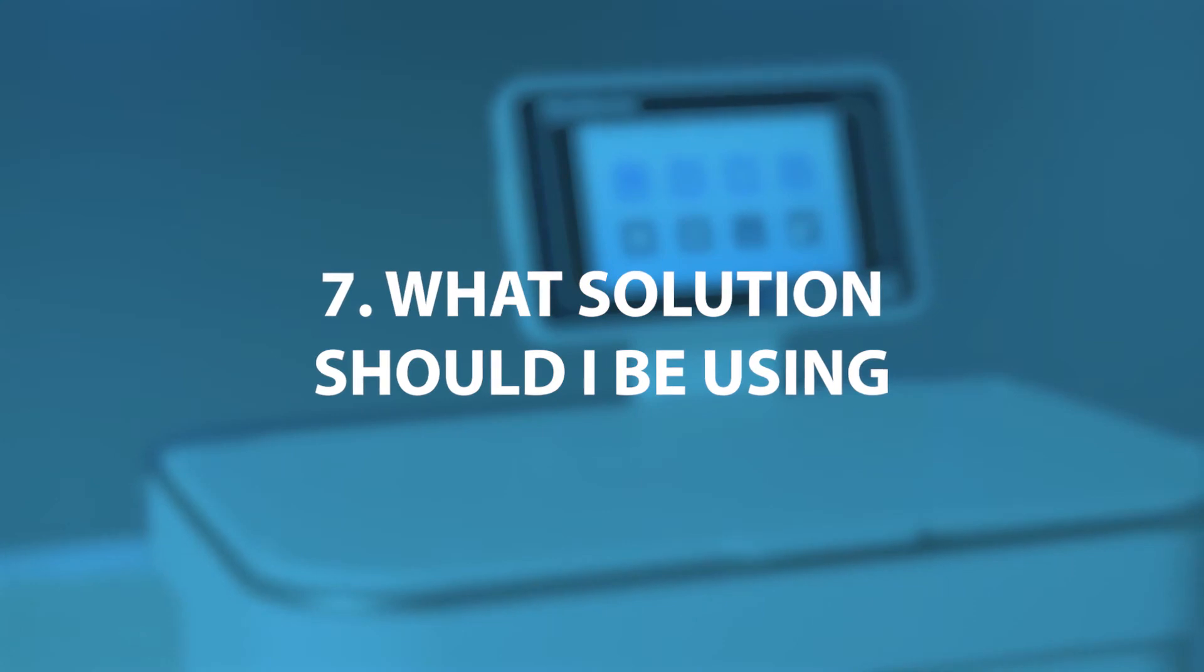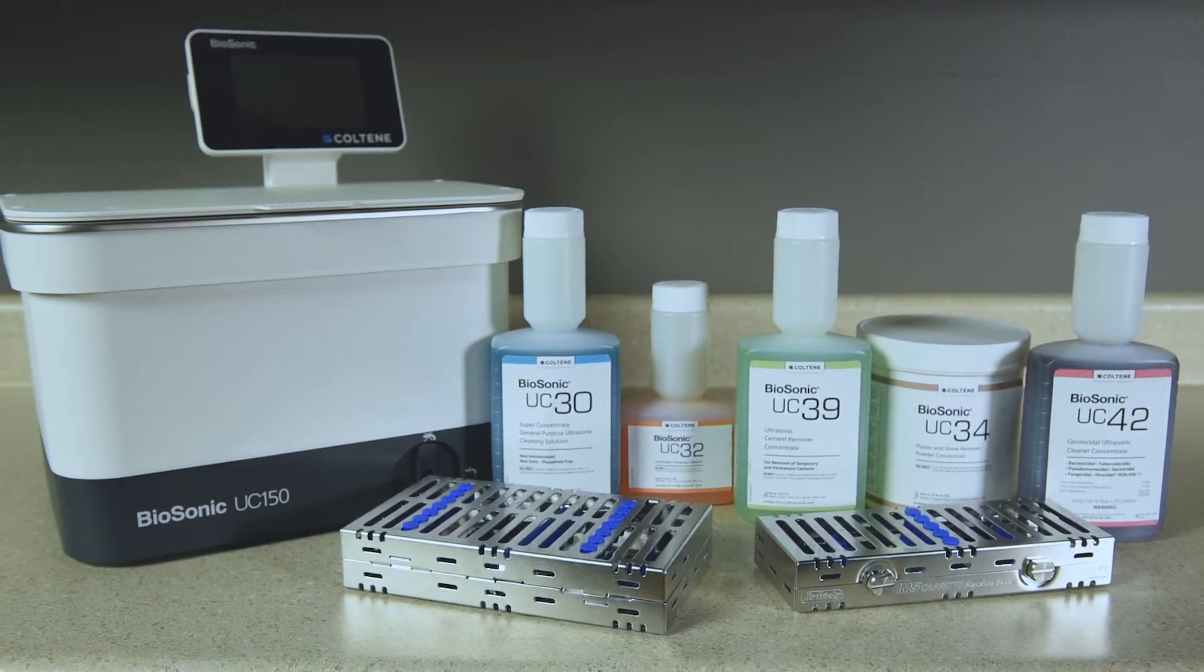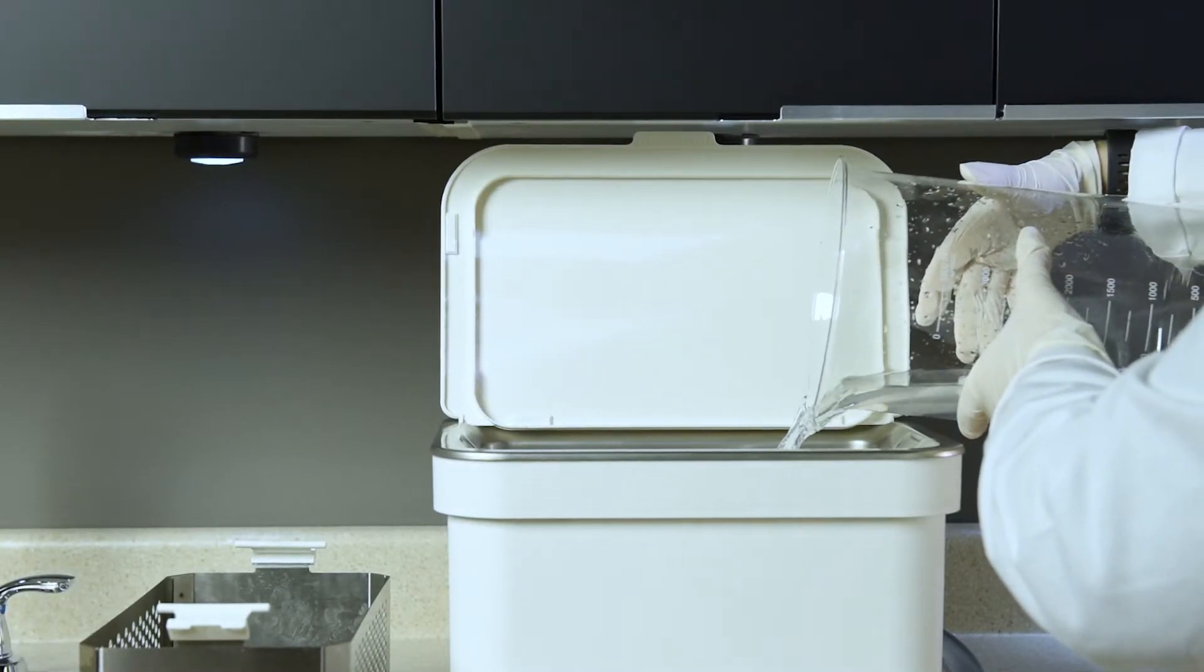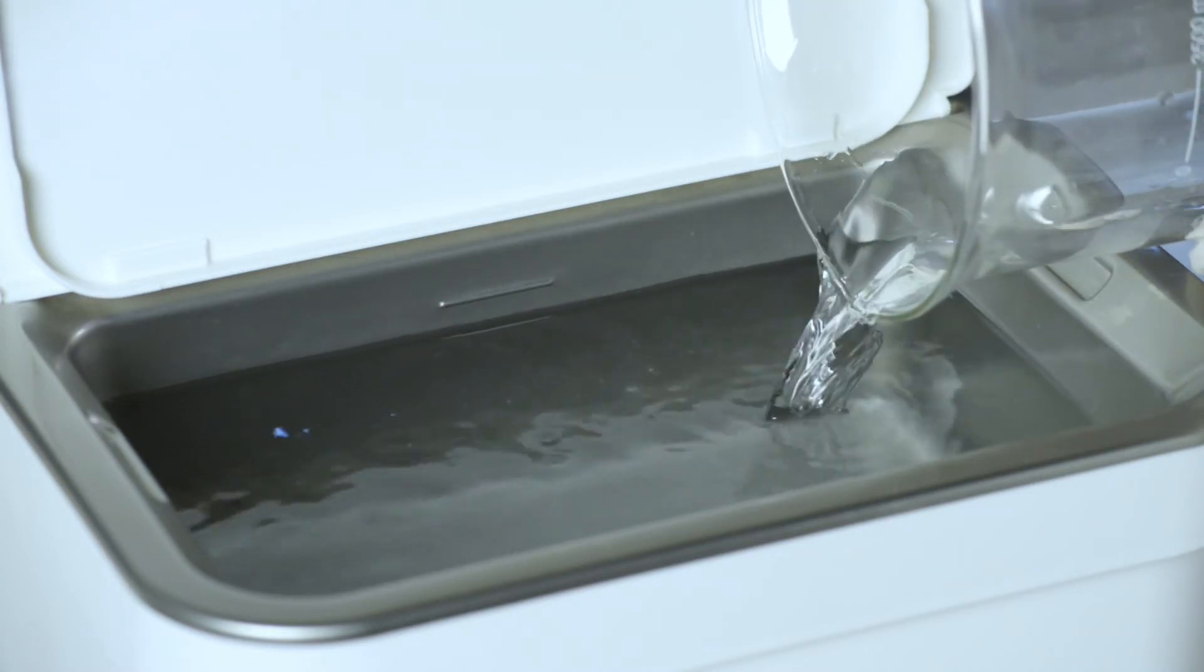What solution should I be using? The purpose of the solution is to break the bonds between the instruments and the soil. Water alone has no cleaning properties and has high surface tension, which inhibits the cavitation bubbles from developing.